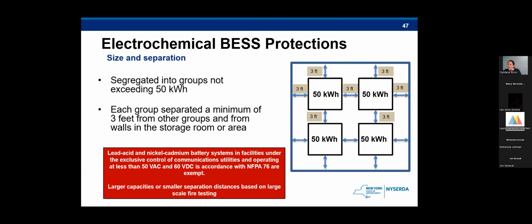So here we have the size and separation requirement. Grouping of energy storage systems to a maximum of 50 kilowatt hours is there to reduce the fire load of a group or a rack. This grouping does not apply to remote outdoor installations, which I think is important to flag. It does, however, apply to walk-in containers or cabinets that are outdoor and near other exposures. So walk-in units that are near exposures, while they need to have spacing between groups, don't need spacing between a group and the wall of the walk-in unit. This also applies to energy storage systems that are in rooms or areas that are indoors.